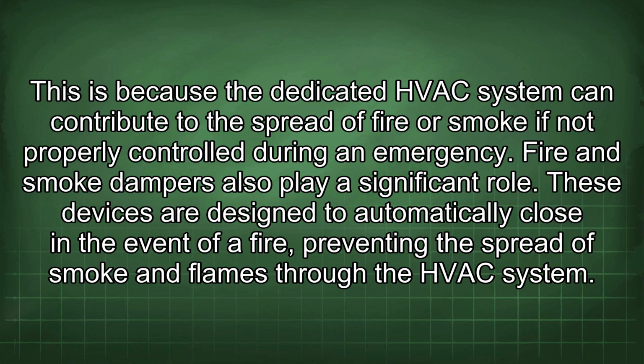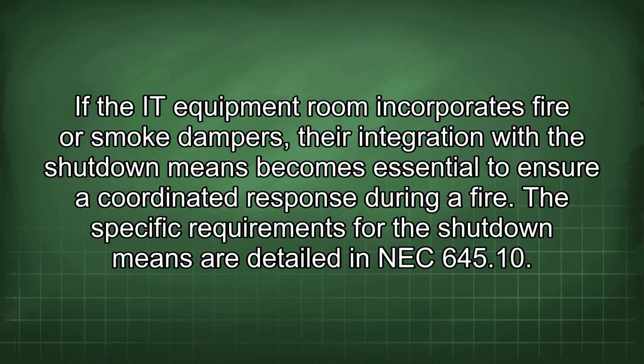These devices are designed to automatically close in the event of a fire, preventing the spread of smoke and flames through the HVAC system. If the IT equipment room incorporates fire or smoke dampers, their integration with the shutdown means becomes essential to ensure a coordinated response during a fire.